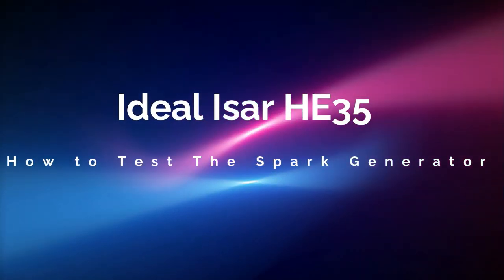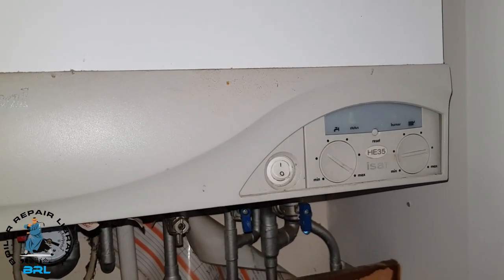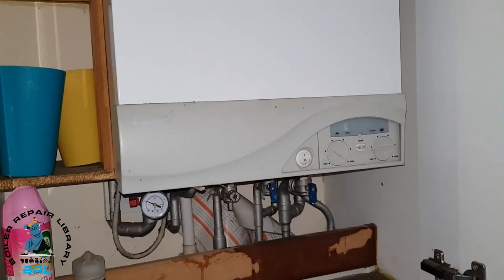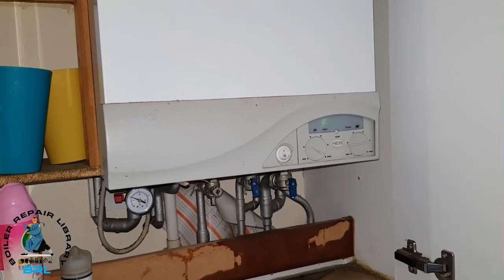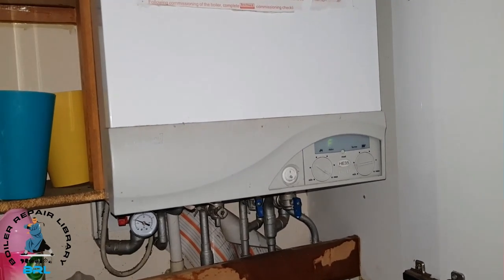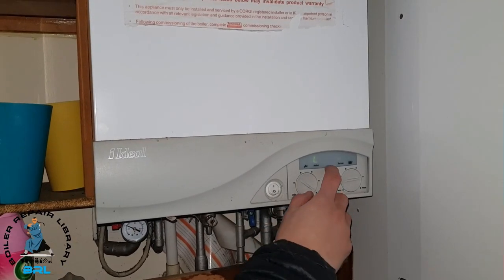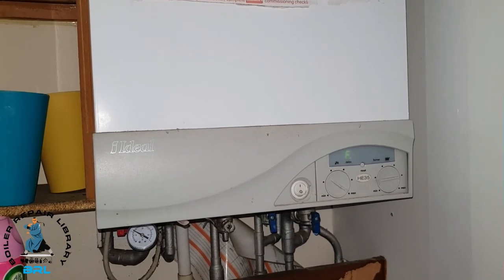In today's video we're looking at an Ideal Isar HE35. The problem is you can see at the front we've got this LF fault code displaying here. We're going to investigate how to fault find on this, and Miles is going to be talking through it as part of his training. We're going to restart the sequence by pressing the reset button and seeing where it goes.